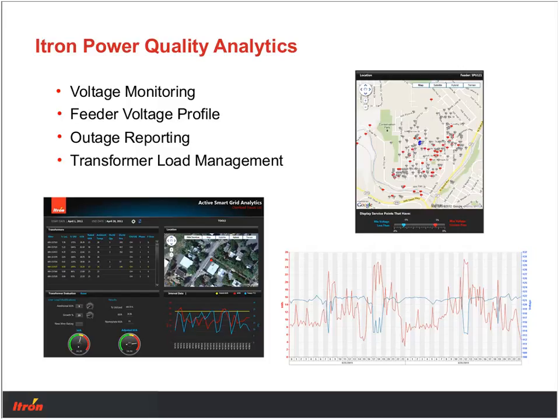Similarly, what we're going to spend even more time on today is this feeder voltage profile, because that's your voltage at every service point on the feeder, as Curt had a few diagrams of earlier. First, in identifying potential feeders for savings, and then after you've identified those and implemented something, how you're actually operating those and seeing that they're working as designed.